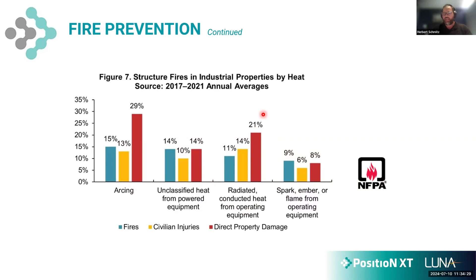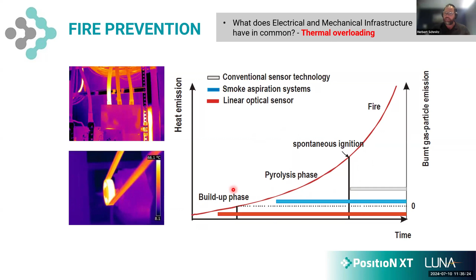So how do these fires actually start in our conveyors? They don't just burst into flame - there is a build-up phase of temperature. As a belt slips over a stationary pulley, it heats up and builds thermal energy, the material starts breaking down in a process called pyrolysis. The gas released is flammable and toxic, and at some point becomes volatile, reaching an ignition point, producing the chemical reaction we call fire. The more thermal energy we have, the more we stay in this cycle. To be preventative, we need to pick up the buildup of thermal energy long before the release of flammable and toxic gases. This phenomenon is similar for electrical infrastructure as it is for conveyor infrastructure.